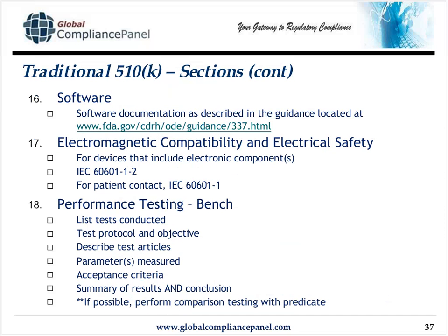Section 16 is software. If your device is software driven, you've got to make sure that you include documentation as provided in the software guidance document. Any EMC or electrical safety information is Section 17.